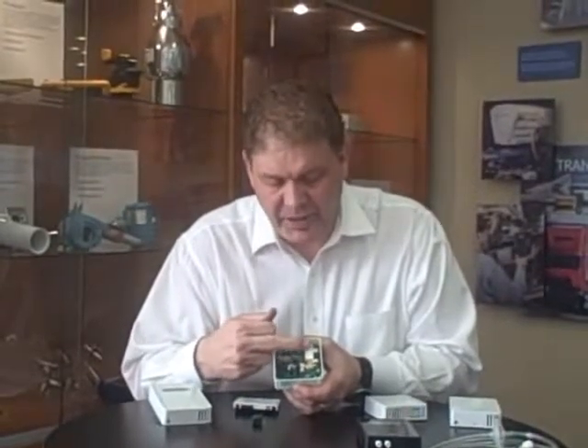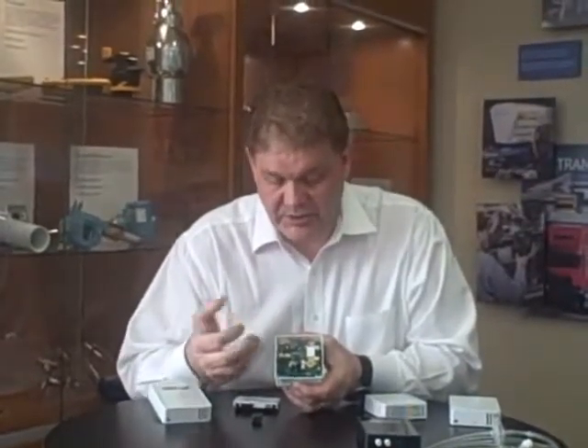One of the big challenges with designing a product like this is that heat is generated both from the power supply and from the CO2 sensor, and that can cause accuracy issues, especially on humidity. What we've done, apart from building a lot of venting in here, is produce a product that actually pulls ambient air across the humidity sensor. Heat rising from the CO2 sensor and the power supply pulls in ambient air from the room below, giving us a much more accurate, repeatable measurement — a mechanical solution to this problem.